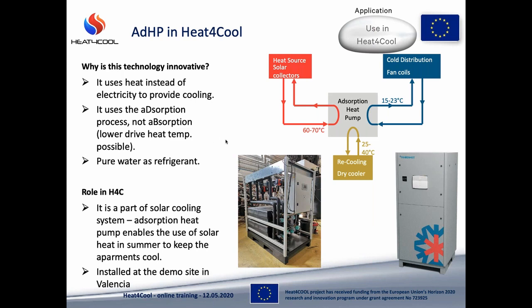In the Heat4Cool project, we have developed a prototype of a new solar-assisted adsorption heat pump, as shown in this picture. Our machine is also installed at one demo site, the demo site in Valencia. There, our heat source is solar collectors. We dissipate the heat in the dry cooler installed on the roof, and the generated cooling effect is used for air conditioning with fan coils.